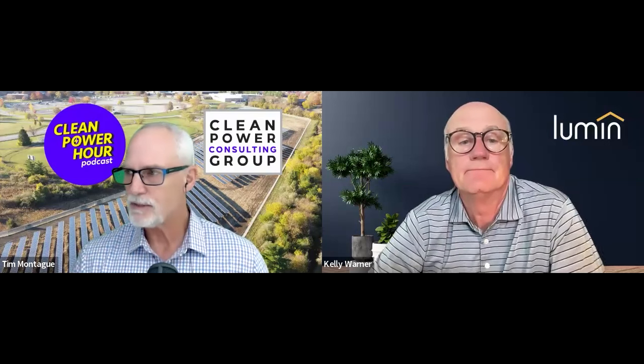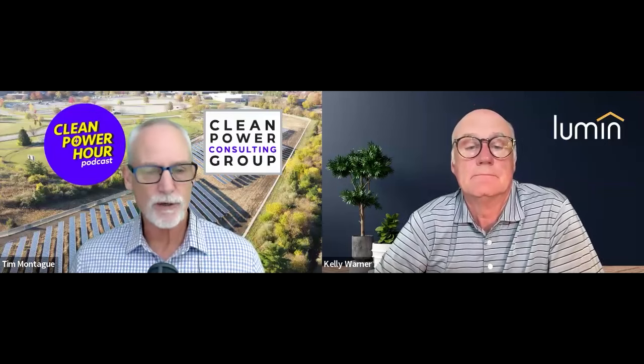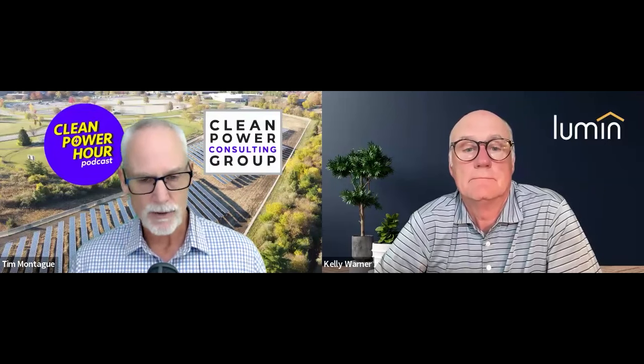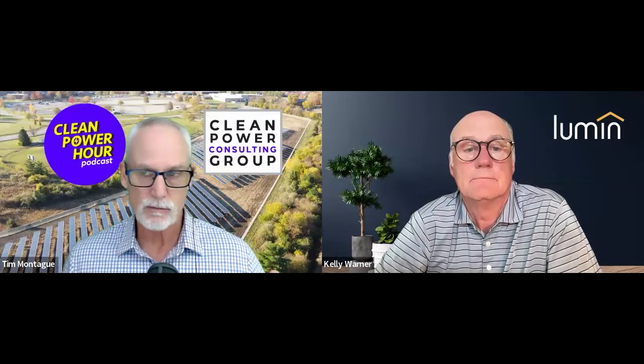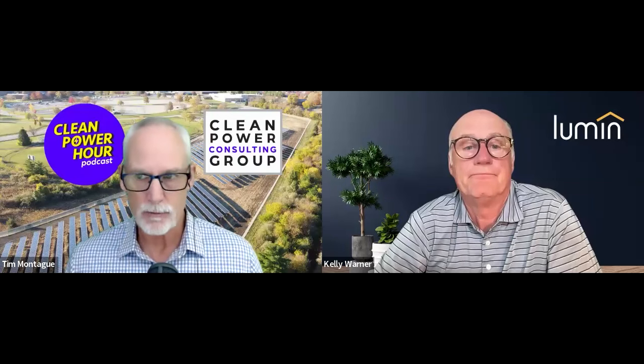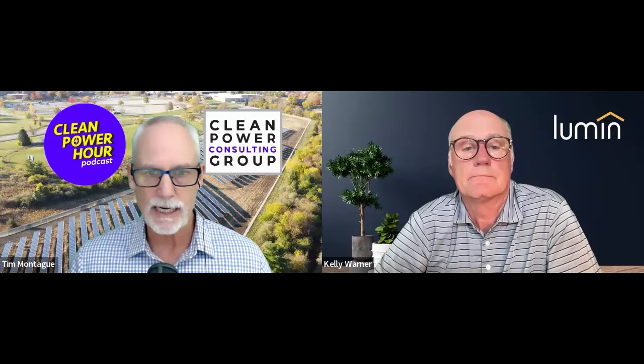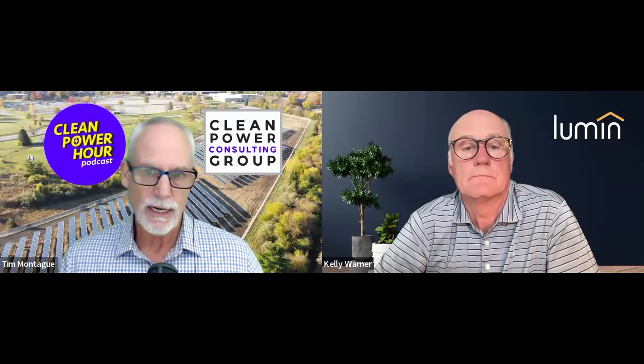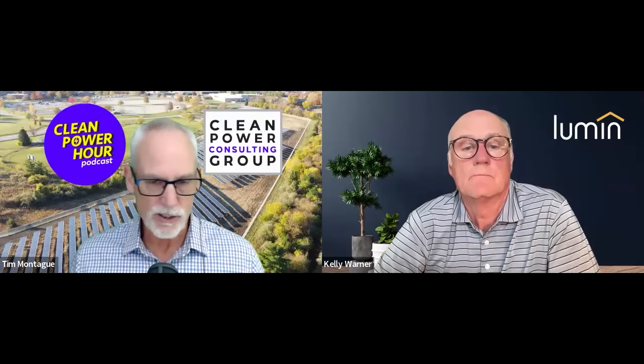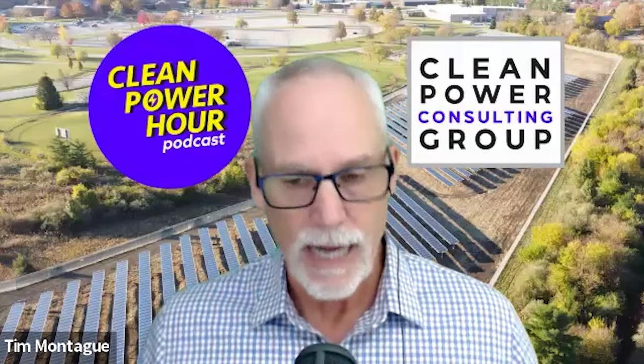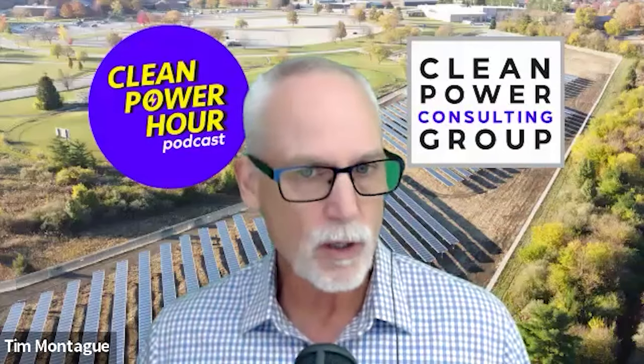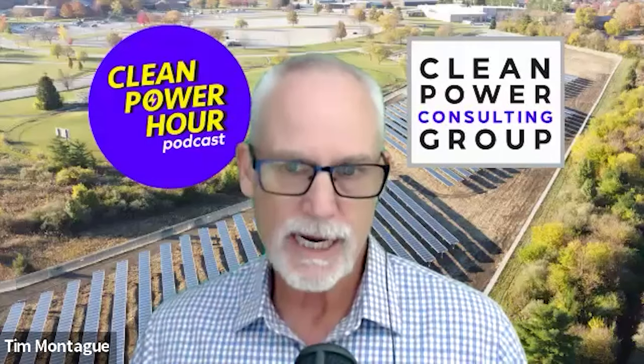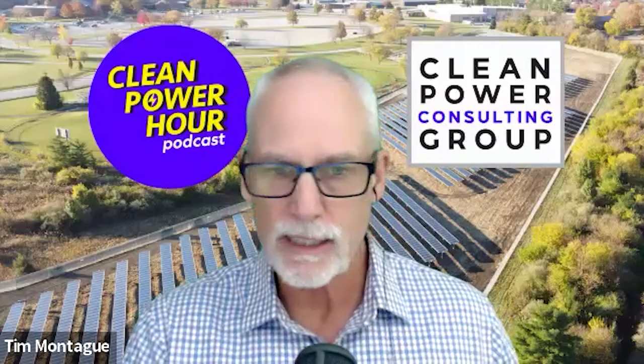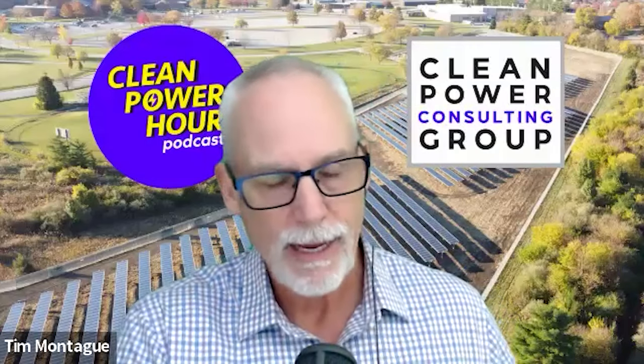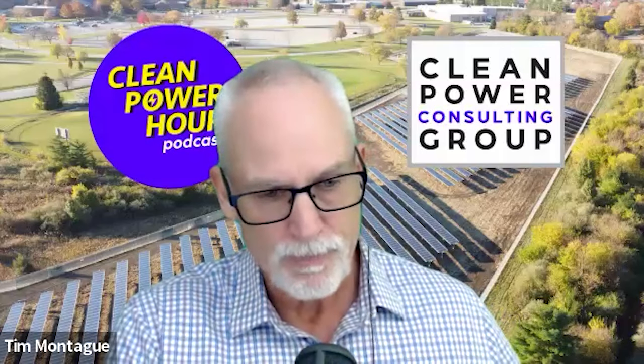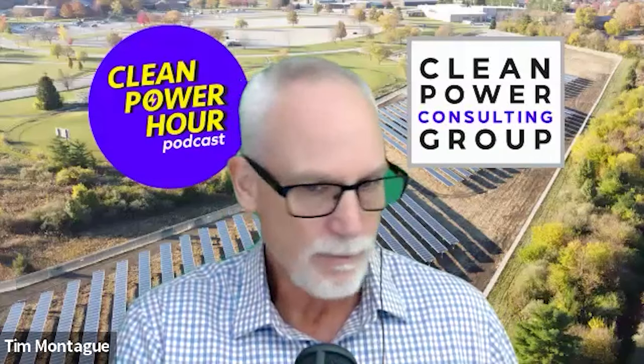So I would love to just geek out for a second. When you're adding solar and battery, solar alone is nice, right? But you have no backup then. When the grid goes down, the solar disconnects by code, and you're without power whether the sun is shining or not if the grid is down. Add a battery and microgrid hardware, and when the grid goes down the system isolates from the grid. Let's say it's daylight and the battery is picking up any local load combined with the solar.